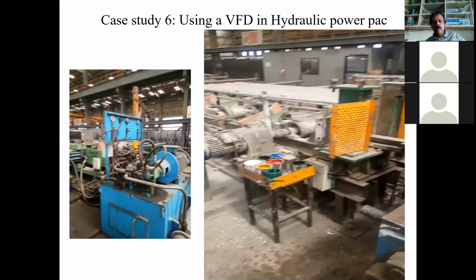So there is a bypass to the hydraulic control, bypass back to the tank. In that process, it is a 75 kilowatt motor, and it is consuming almost 42 kilowatts during the idle operation. This requires some careful planning. So we need to do a cycle time analysis, list down the various processes where hydraulics are required, how many seconds or minutes this pressing or elongation will be required, and what the idle times are, and how we can use perhaps a VFD. In this case, a VFD was used. So when no action is taking place, reduce the speed, and completely avoid the bypass circulation of the oil back to the tank.